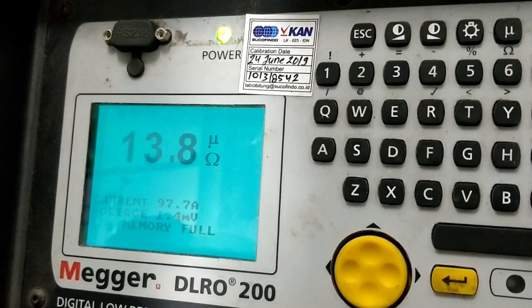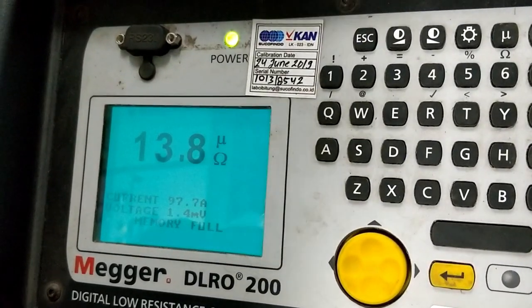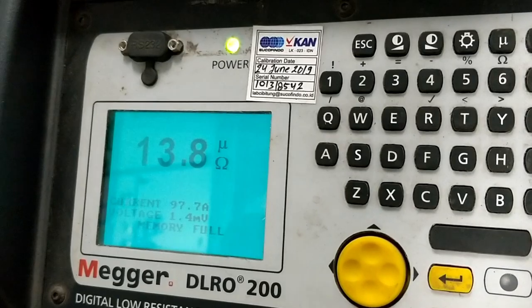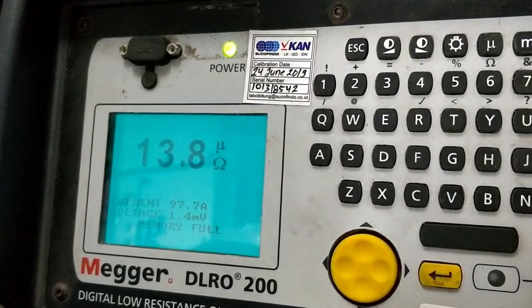Now I got the value 13.8 micro ohm and current injected is 97.7 amps. Drop voltage is 1.4 mV.